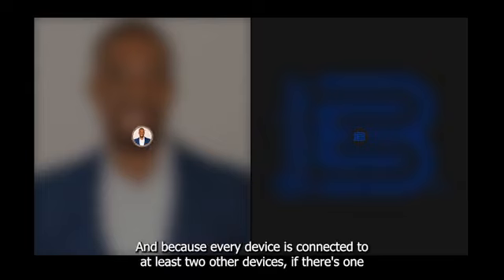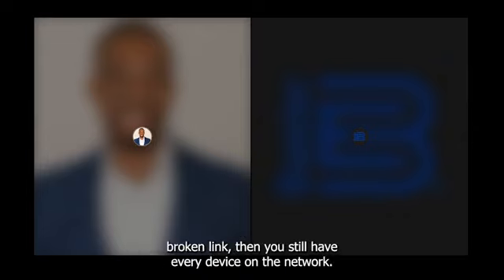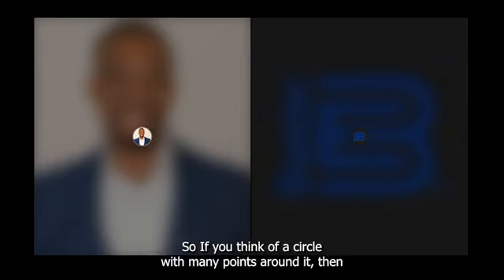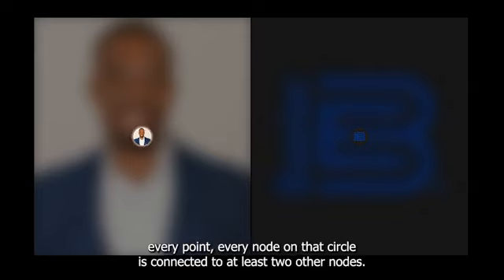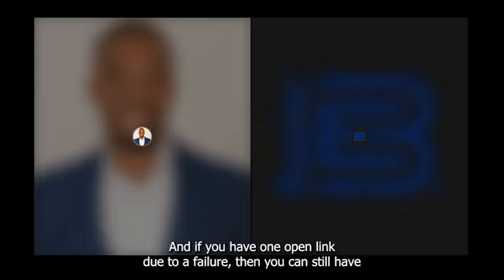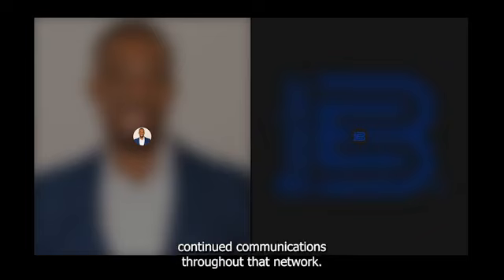And because every device is connected to at least two other devices, if there's one broken link, you still have every device on the network. So if you think of a circle with many points around it, every node on that circle is connected to at least two other nodes. And if you have one open link due to a failure, you can still have continued communications throughout that network.